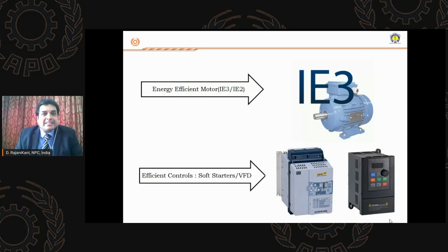For the starting of these motors, you have VFD control and soft starters. To control the inrush current when a motor is started, you can start the motor so softly that there is no inrush, and there won't be much loading on your plant. Maximum demand also increases if you start all these motors at a time. So going for a soft starter is one efficient technology that is available and proven in the market.